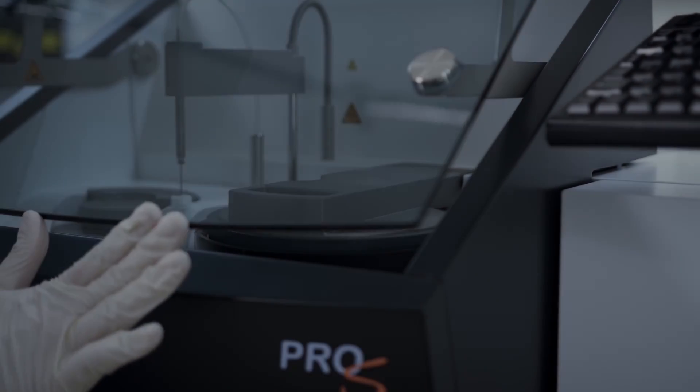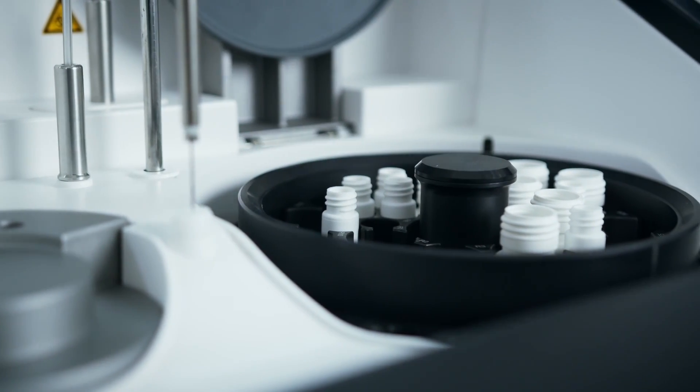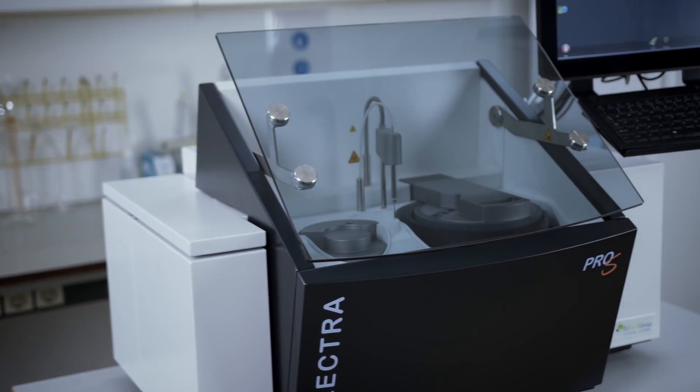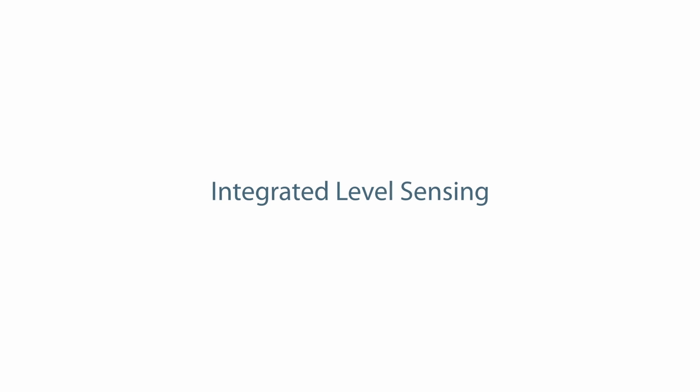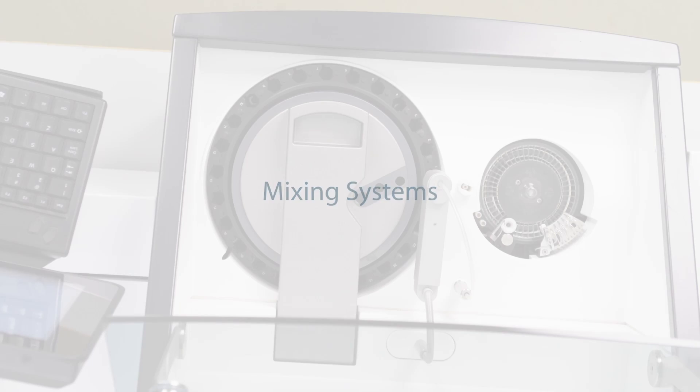The reusable and economical cuvette rotor with washer and optical systems features 48 cuvettes, and the measuring temperature is controlled at 37 degrees Celsius. It also includes integrated level sensing, pipetting, reagent, preheat, and mixing systems.